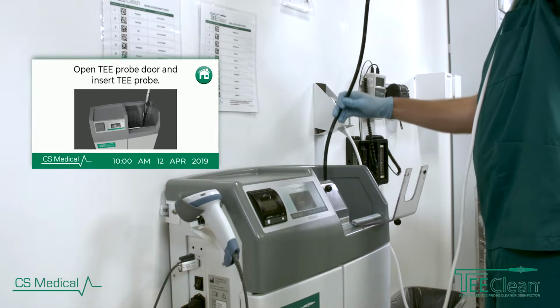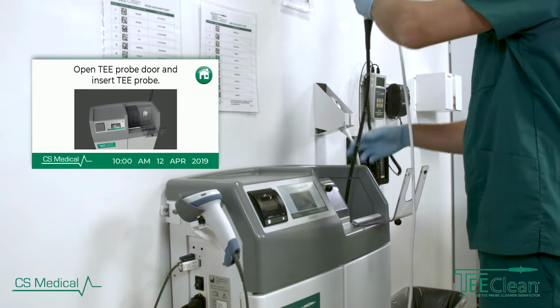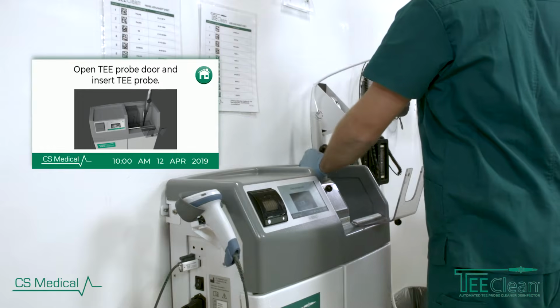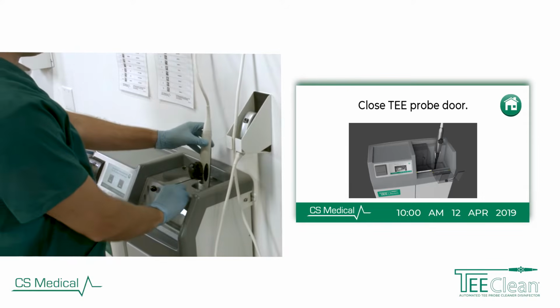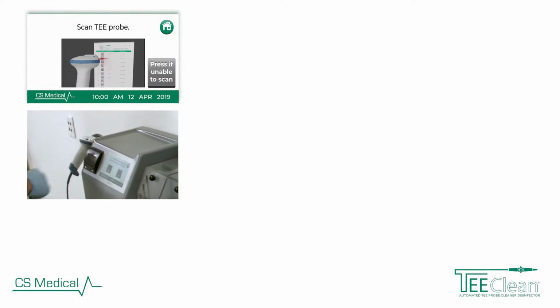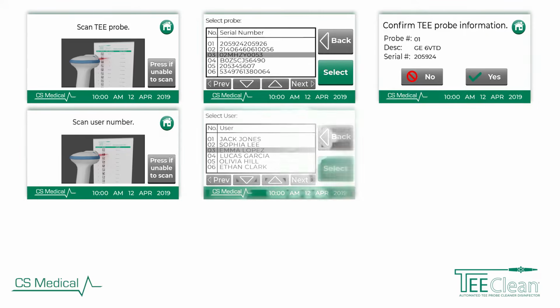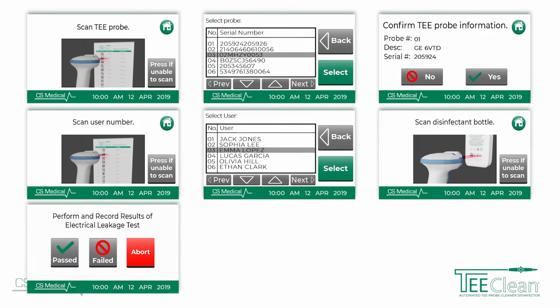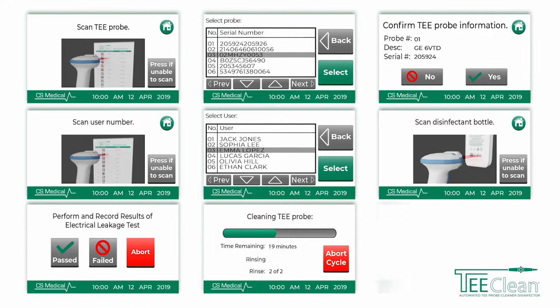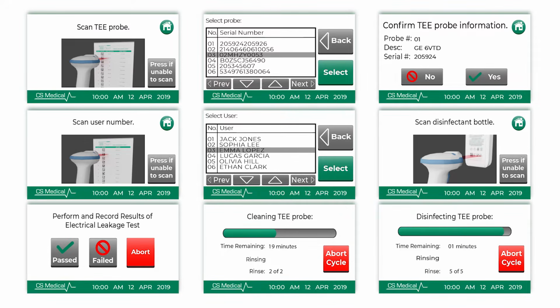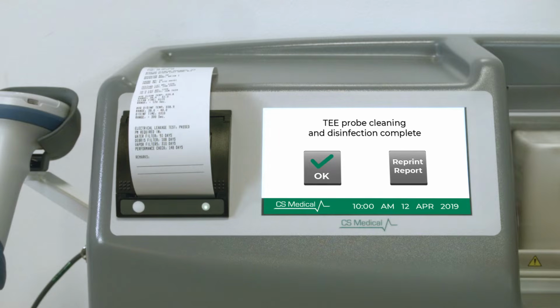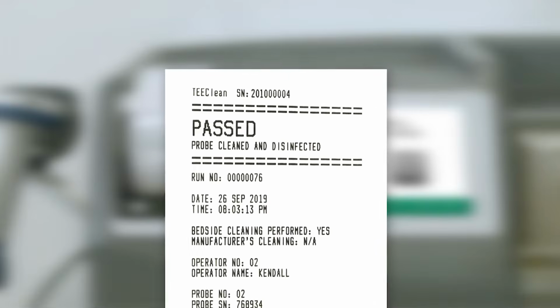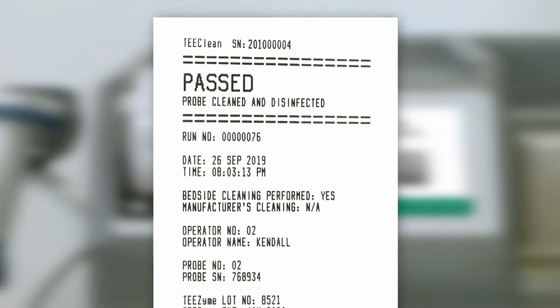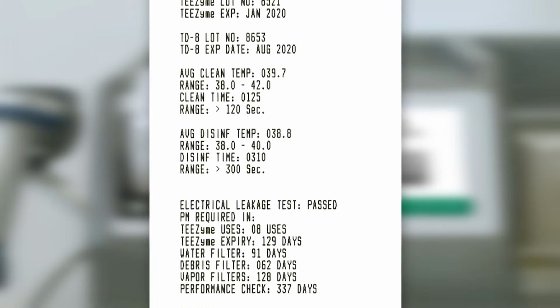To use TEEClean, simply place the bedside enzymatically treated soiled TEE probe directly into TEEClean. No additional steps required. Then, by following simple prompts on the color LCD display, the healthcare professional will enter information about the probe, disinfectant chemistry used for high-level disinfection, and if the probe passed electrical leakage testing. This data, in addition to other system data, will be printed on the reprocessing report at the conclusion of a completed cleaning and disinfection cycle.